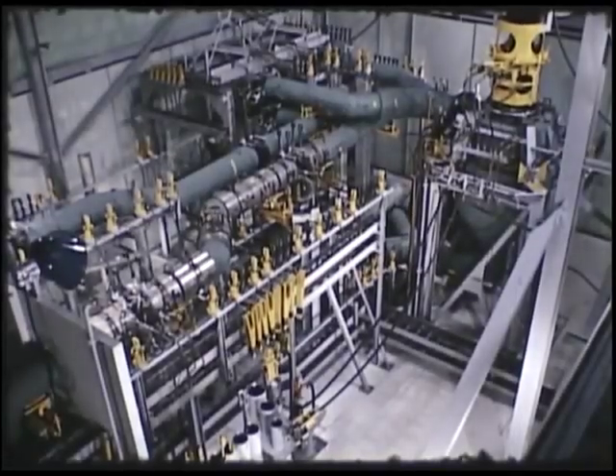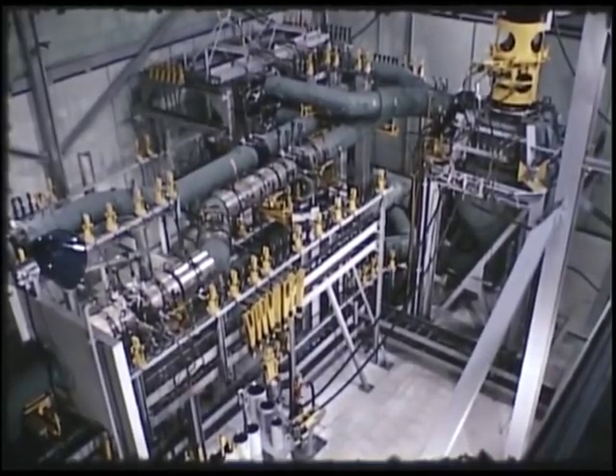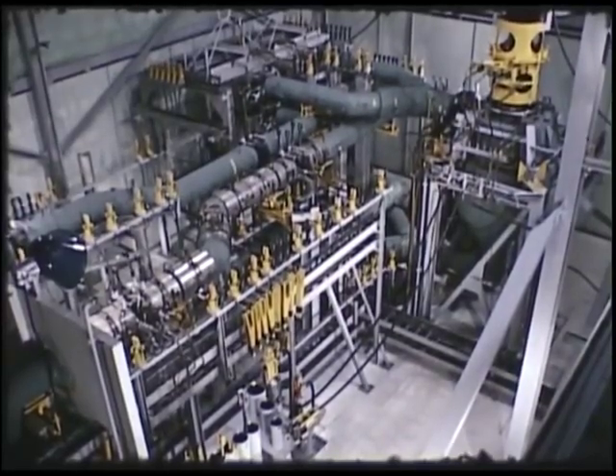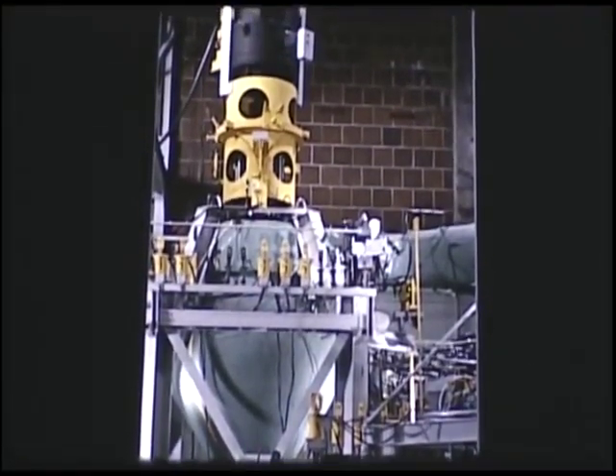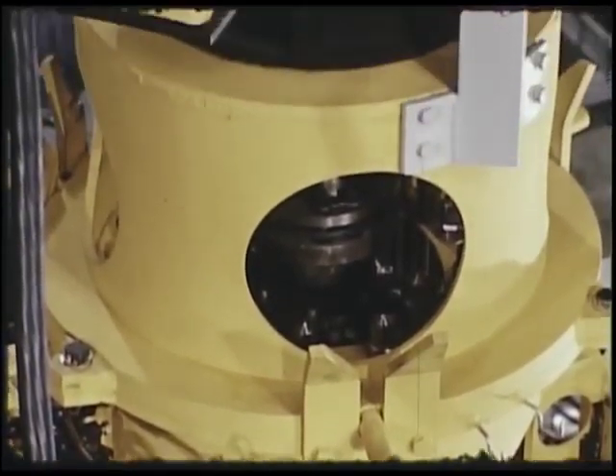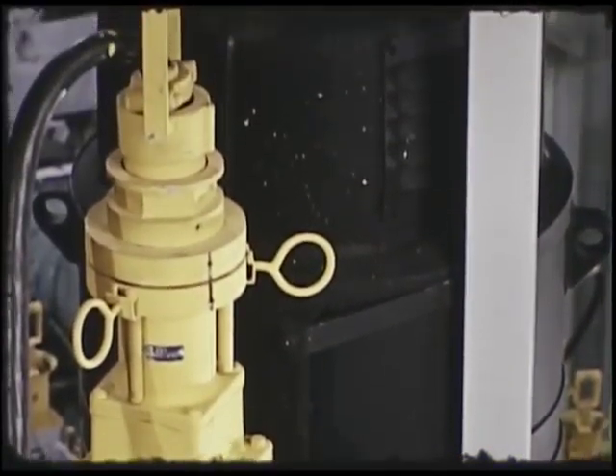This facility is a mock-up of a small reactor system, approximately 20 thermal megawatts in size. A simulated fuel mixture of sodium fluoride, zirconium fluoride, and uranium fluoride was circulated through the loop at 1200 degrees Fahrenheit and at 5 pounds per square inch helium blanket pressure. Components include a reactor core vessel, which supports a centrifugal sump pump and a 30 horsepower DC motor. The pump impeller circulates 460 gallons of molten salt per minute at 28 feet of head. The motor operates at 1,300 revolutions per minute.